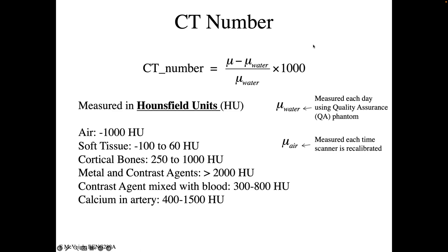So what we're going to wind up with is estimates of the linear attenuation coefficient mu for our target voxel and whatever material is in that voxel, be it muscle, bone, water, we're going to get a mu value. And in the early days of CT, this was in the 70s, computers really worked on integers efficiently, not floating point. So what they did was, instead of just displaying the mu value, they displayed it as a fractional change from the water mu value.